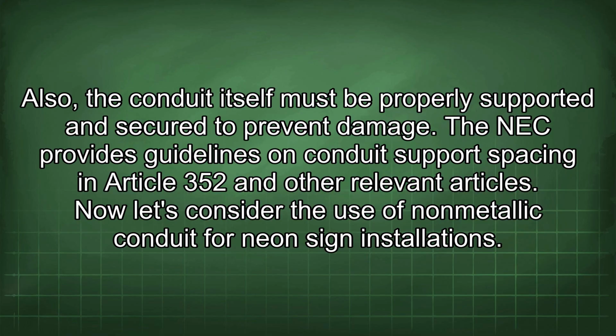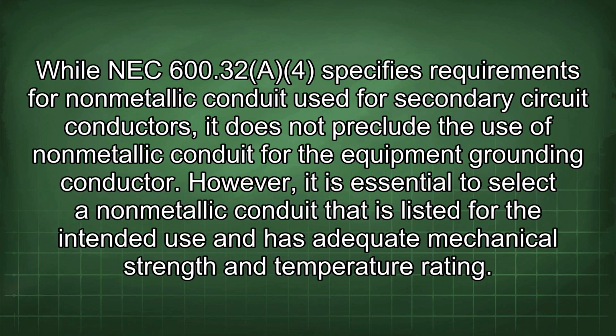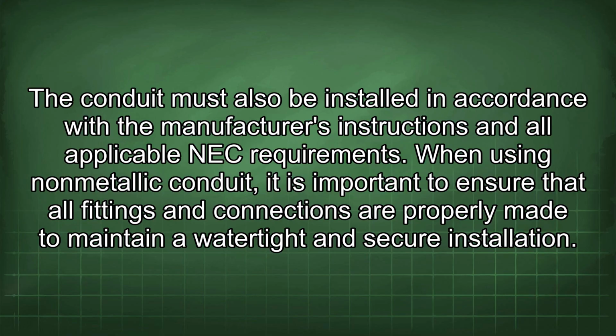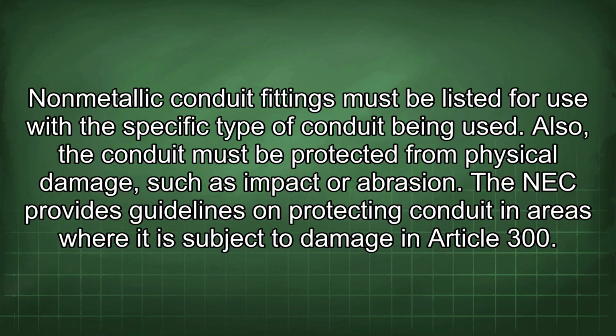Now let's consider the use of nonmetallic conduit for neon sign installations. While NEC 600.32 specifies requirements for non-metallic conduit used for secondary circuit conductors, it does not preclude the use of non-metallic conduit for the equipment grounding conductor. However, it is essential to select a non-metallic conduit that is listed for the intended use and has adequate mechanical strength and temperature rating. The conduit must also be installed in accordance with the manufacturer's instructions and all applicable NEC requirements. When using non-metallic conduit, it is important to ensure that all fittings and connections are properly made to maintain a watertight and secure installation. Non-metallic conduit fittings must be listed for use with the specific type of conduit being used. Also, the conduit must be protected from physical damage such as impact or abrasion. The NEC provides guidelines on protecting conduit in areas where it is subject to damage in Article 300.